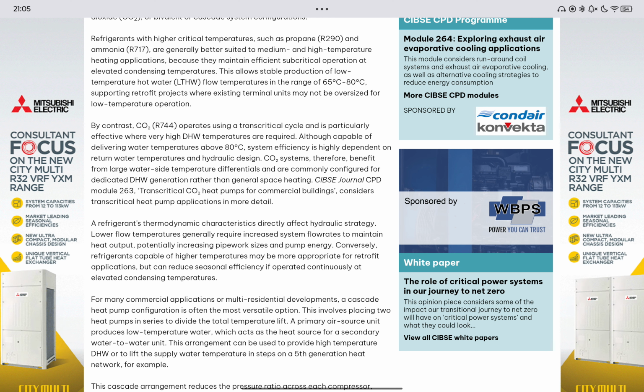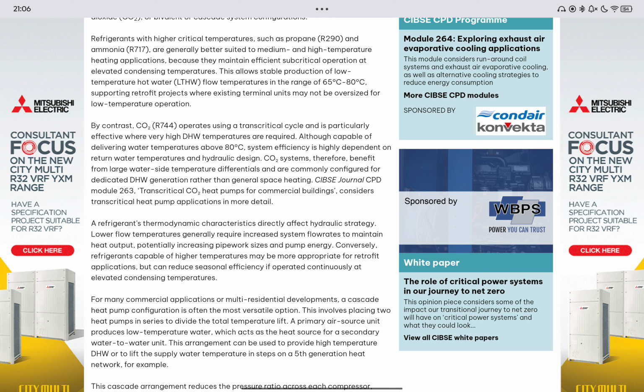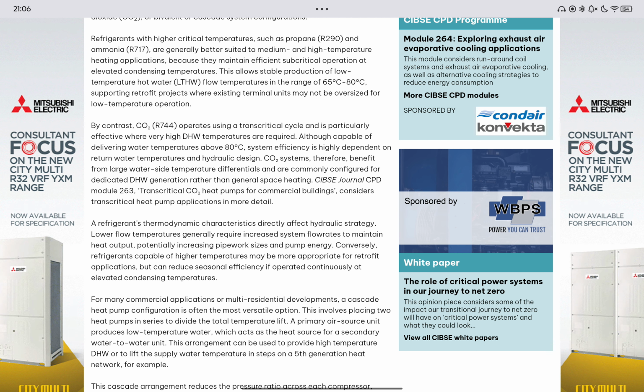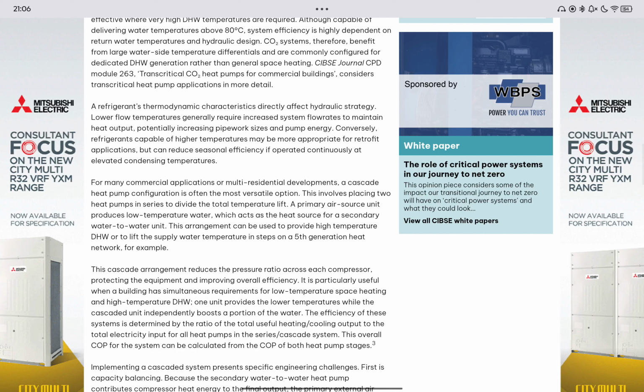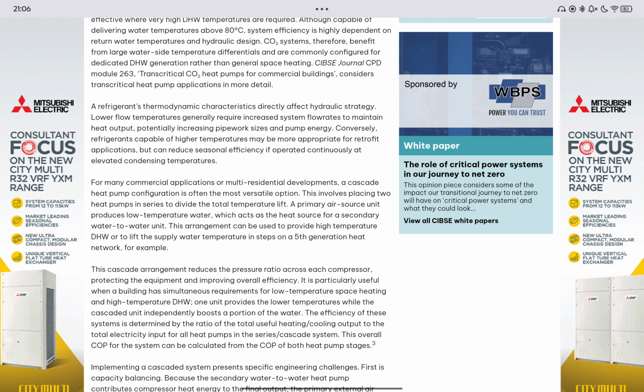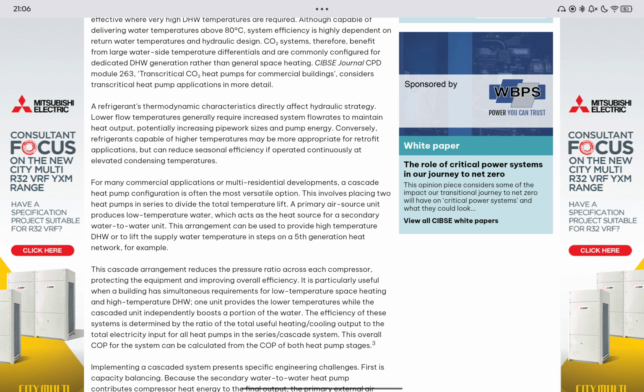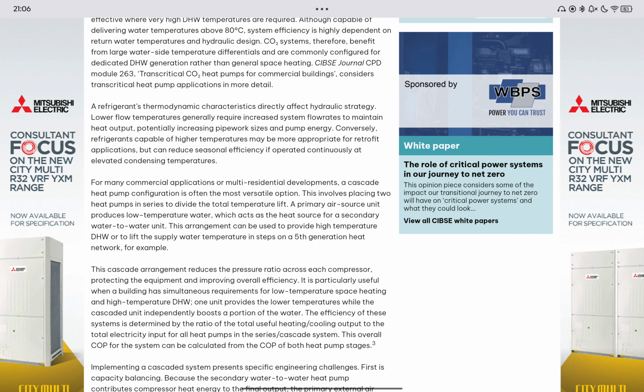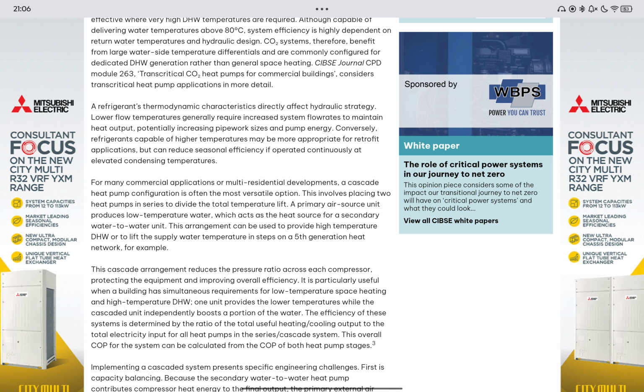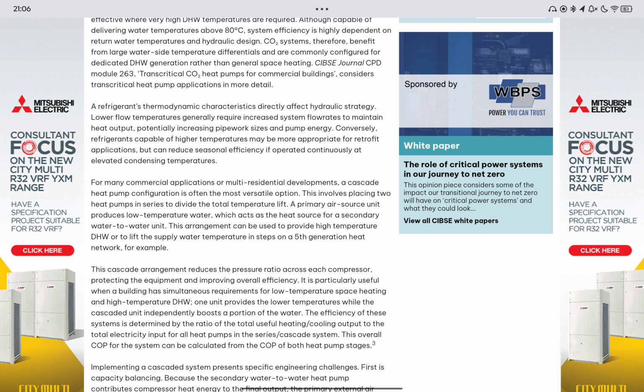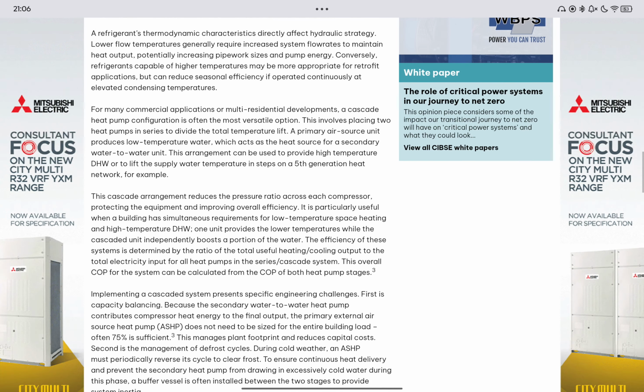CIBSE Journal CPD Module 263, Transcritical CO2 Heat Pumps for Commercial Buildings, considers transcritical heat pump applications in more detail. A refrigerant's thermodynamic characteristics directly affect hydraulic strategy. Lower flow temperatures generally require increased system flow rates to maintain heat output, potentially increasing pipework sizes and pump energy. Conversely, refrigerants capable of higher temperatures may be more appropriate for retrofit applications, but can reduce seasonal efficiency if operated continuously at elevated condensing temperatures.